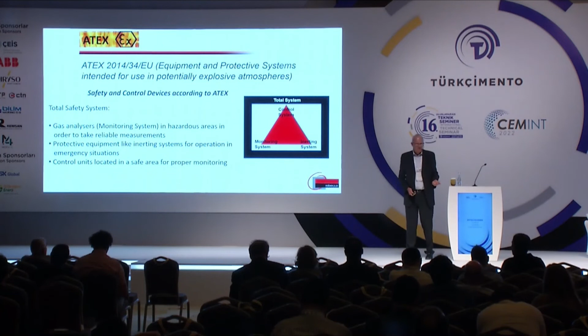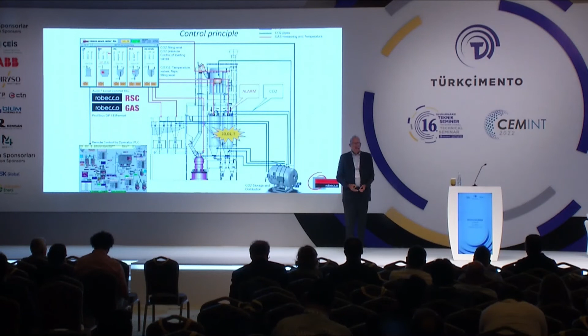Very clear. Here is the control principle, a short sketch showing different measuring points. You see these red lines—these are the measuring points that might be at the entrance of the mill, at the baghouse, at the outlet of the baghouse, or even directly at the silos. All these measuring systems send their data to a so-called secure system, an external system in order to monitor and control all the technical values coming from the process. That means if there is a certain value in terms of oxygen or carbon monoxide increasing or exceeding a certain threshold, the system automatically activates an injection of inerting gas into the system. This is the control principle.